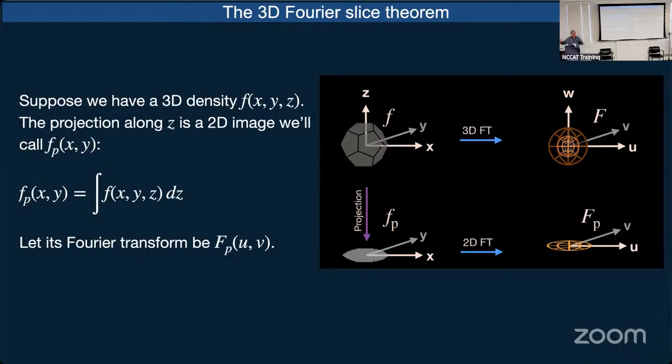You project one of those 2D projections through the room in one direction, and then from another direction, and from another direction. And you get a sort of blurred reconstruction of the 3D object. Then you can do what's called filtered back projection, where you do these back projections and then operate on them with a particular kind of filter that reweights the Fourier components, and you get a reconstruction.